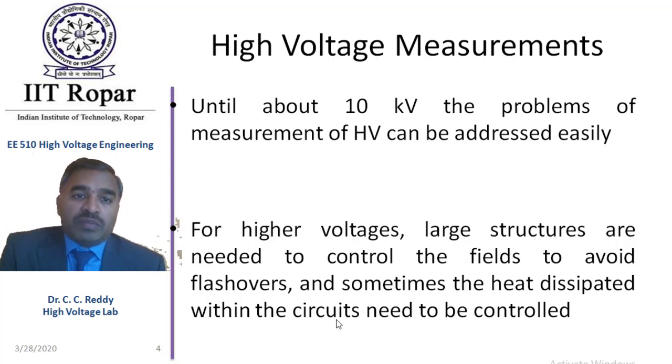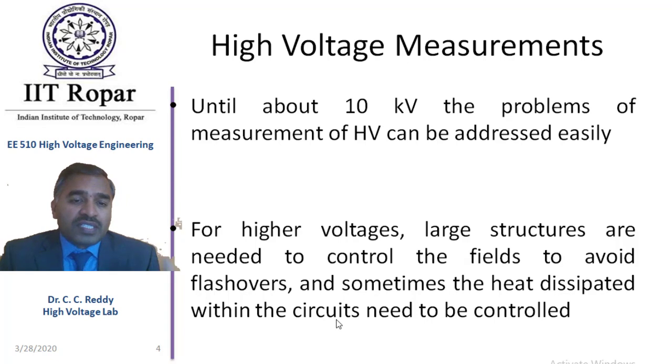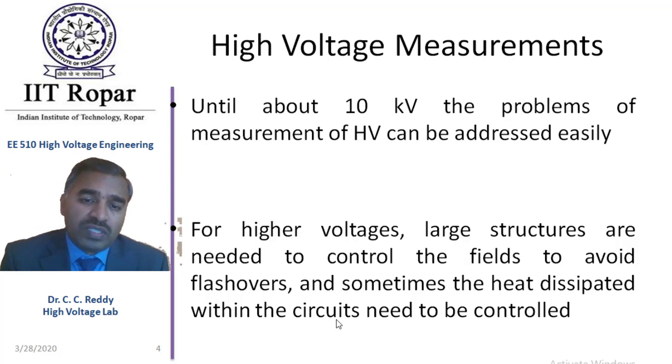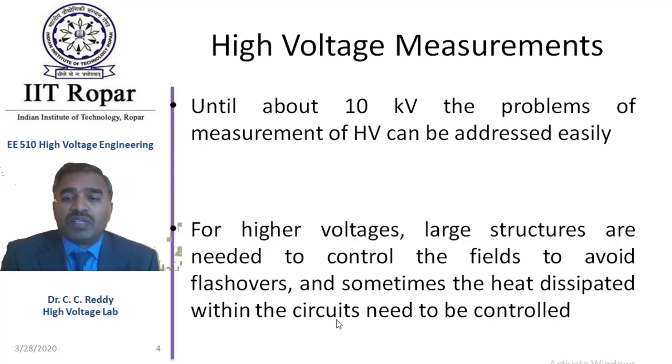High voltage measurements. Until about 10 kilovolts, the problems of measurement of HV can be addressed. But for higher voltages, large structures are needed to control the fields to avoid flashovers, and sometimes the heat dissipated within the circuits needs to be controlled.